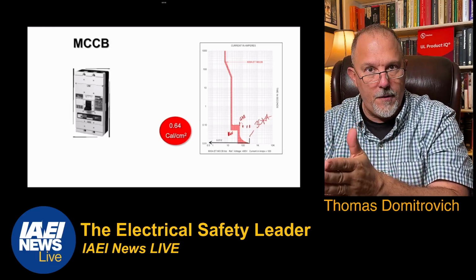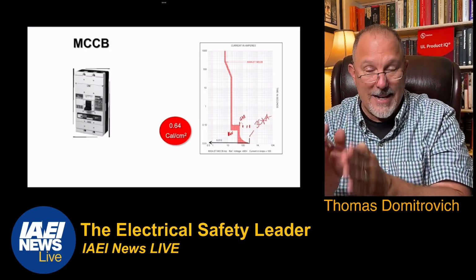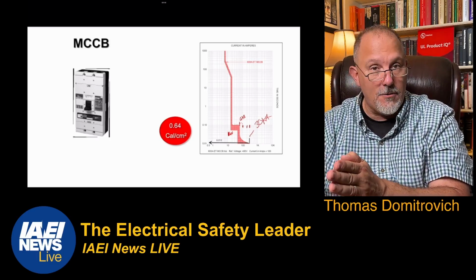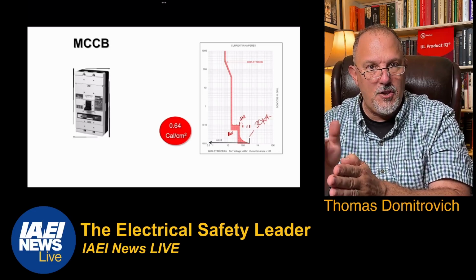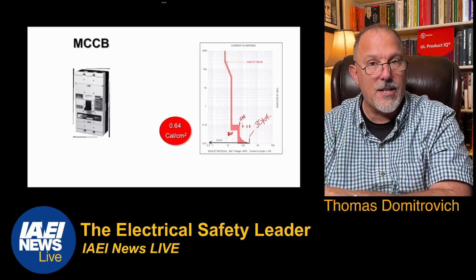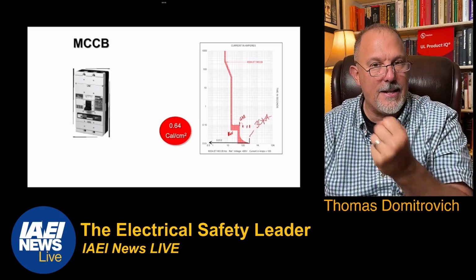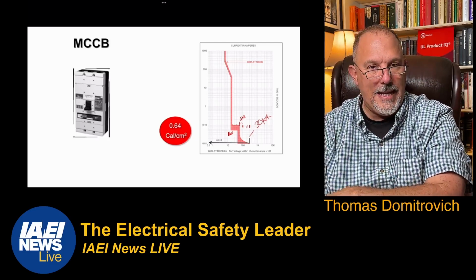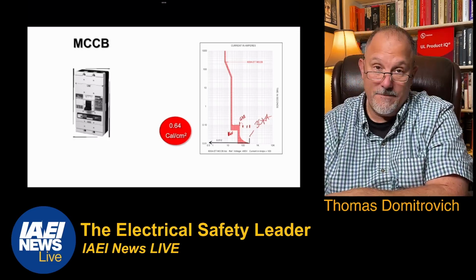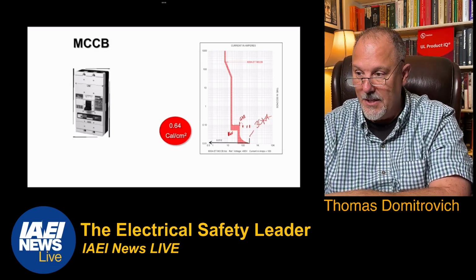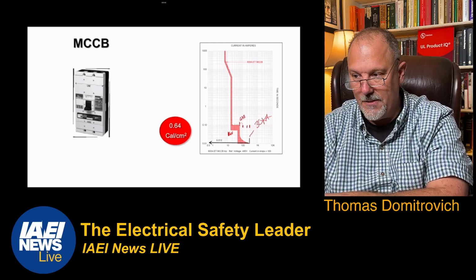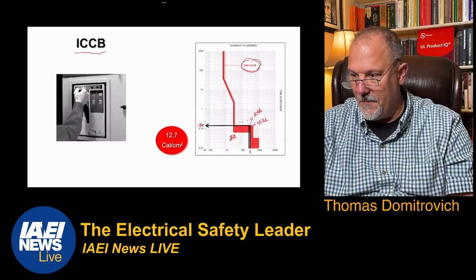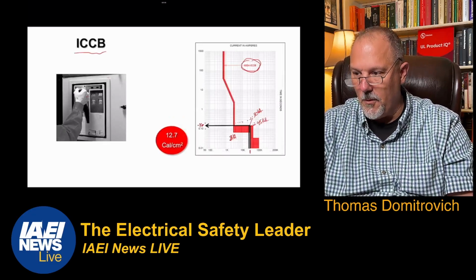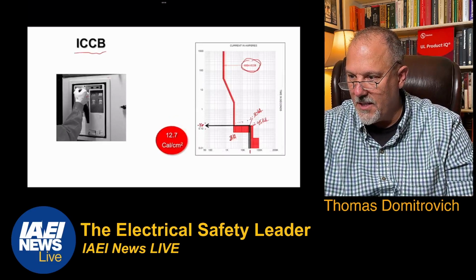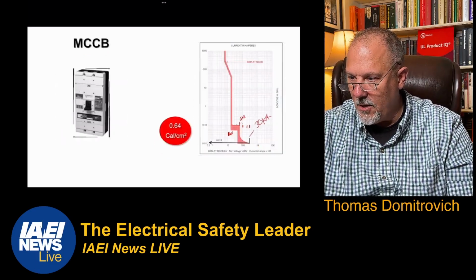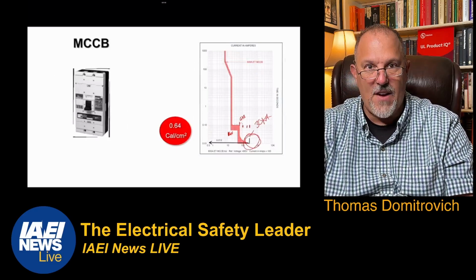So we make a trip curve to protect the circuit breaker. That's what it's there for. I need to clear that fault current where it's possible, and I can't let too much current flow through this device for too long, else I have too many magnetic forces and it cannot hold itself together. So in many cases, the trip curve settings are there to protect the device itself. It can't withstand high fault currents for very long periods of time. This is 30,000 amps for 0.1 seconds. Look at this 30,000 amps, I need to take it off very fast.